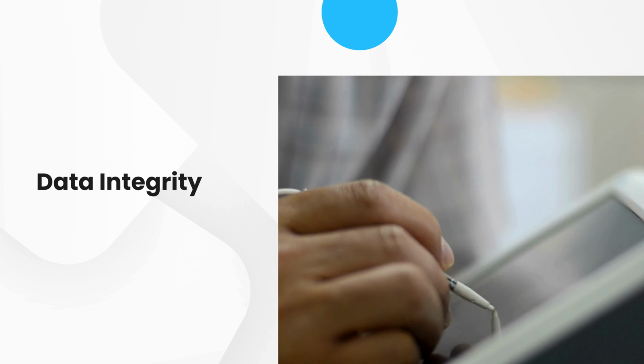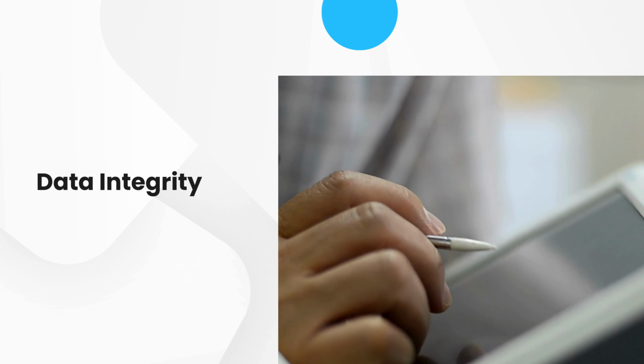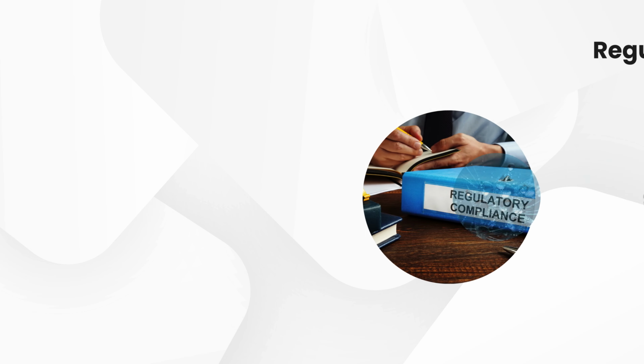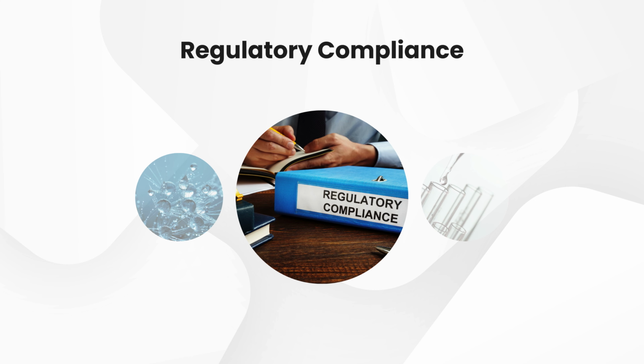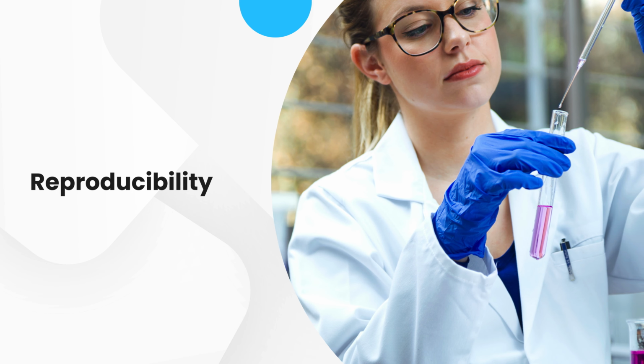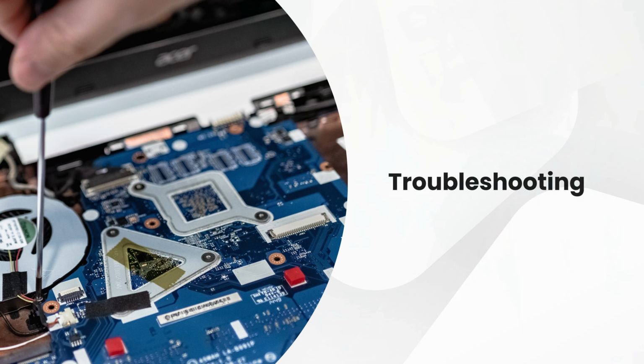validity. Regulatory compliance. In industries like pharmaceuticals, regulatory bodies like the FDA mandate instrument qualification. Reproducibility. Qualification ensures your HPLC produces consistent results over time and across different operators. Troubleshooting. It establishes a baseline for performance, making it easier to identify and resolve problems. The qualification process is broken down into 4 key stages.